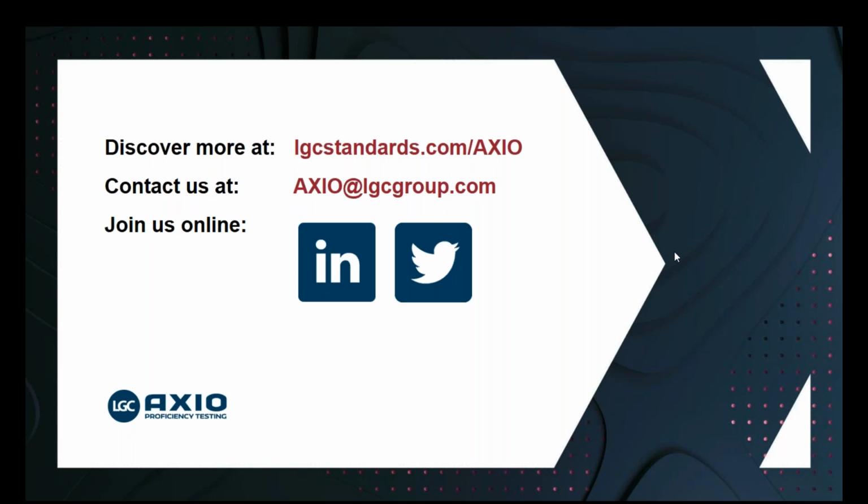Yes, there are other ways we can determine an assigned value if we do have low participant numbers. For some of these reference materials, we can use a certified reference material. We can also use what we call expert laboratories. So we do have some options that allow us to score these laboratories. And the other thing is, if it's a low participation just for their specific methodology, they can compare themselves against peers that are in other methodologies to see how they perform compared to other testing systems. So there are several different ways laboratories can still utilize the report.